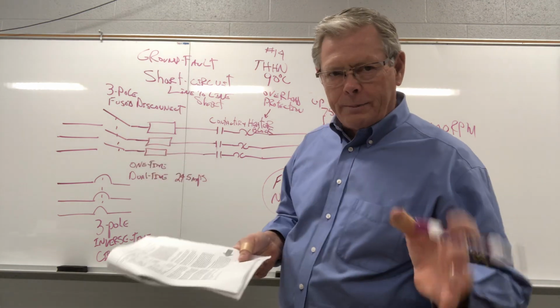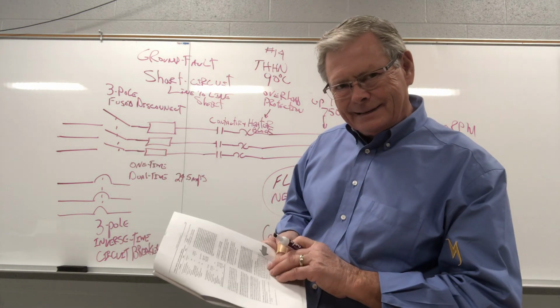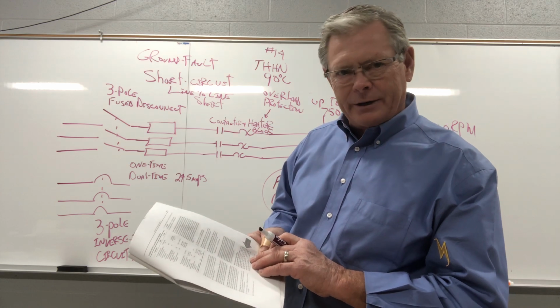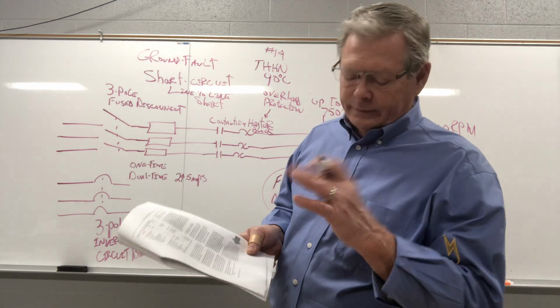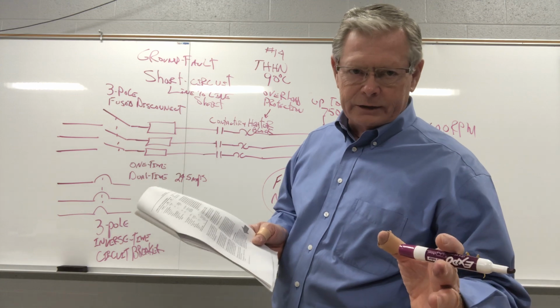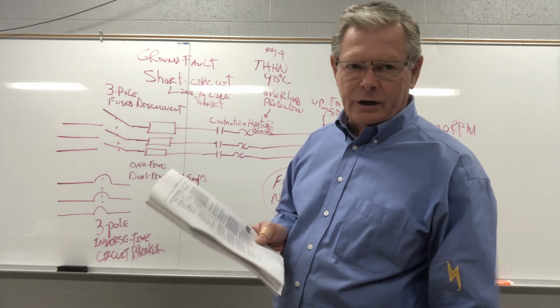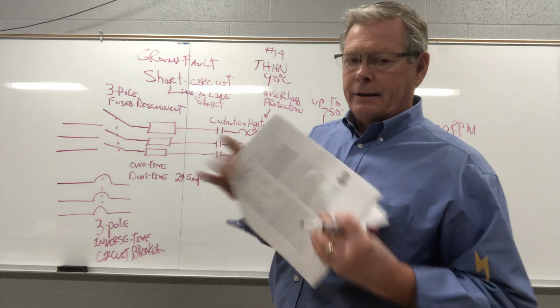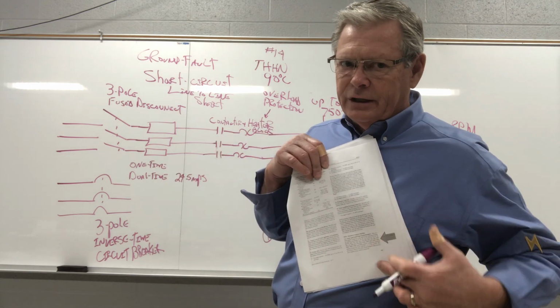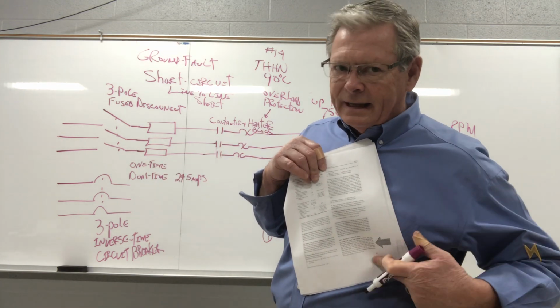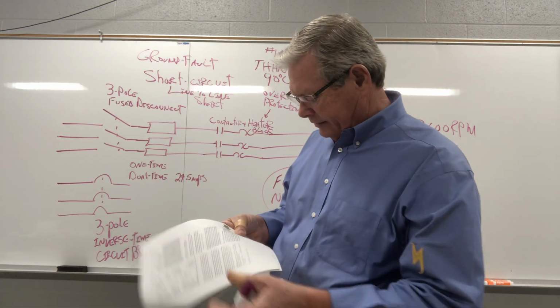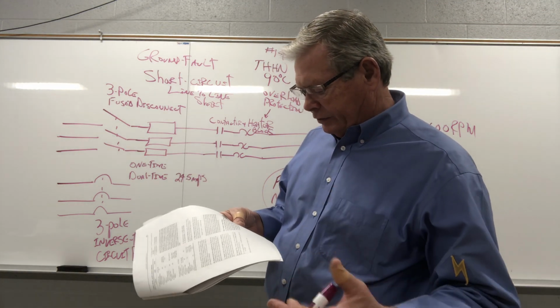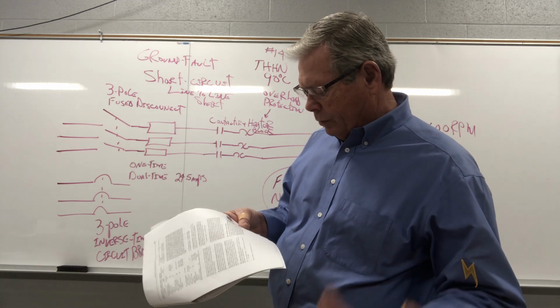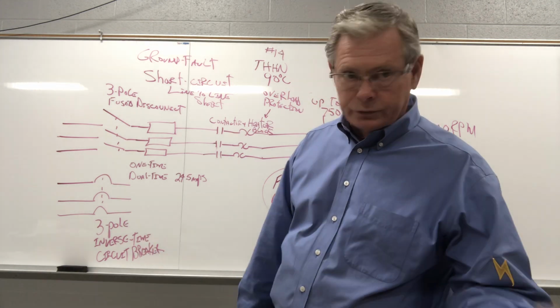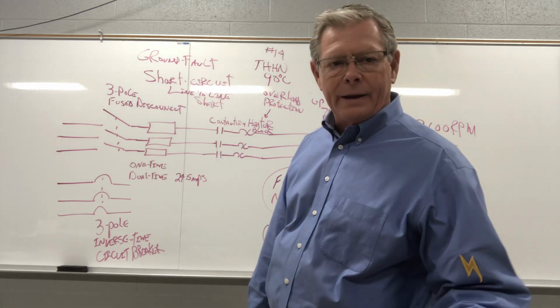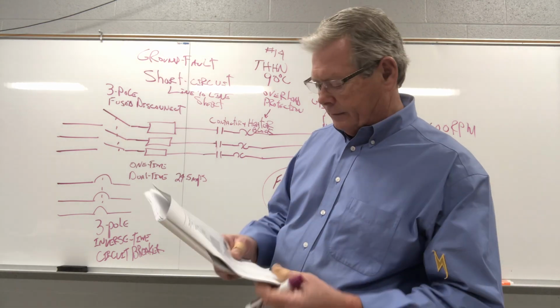So 240.6 gives us a whole list of standard size fuses or breakers. Now, one favorite trick question for electrical licensing is, is 601 amps a standard size fuse? If you look through here, you won't see it in the list, but down at the very bottom, read that last sentence, okay? That last sentence says, additional standard ampere ratings for fuses shall be 1, 3, 6, 10, and 601. So 601 is a standard size fuse. Don't know why they did that, but they didn't call me either, okay?